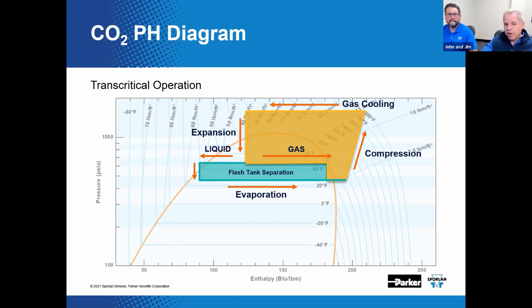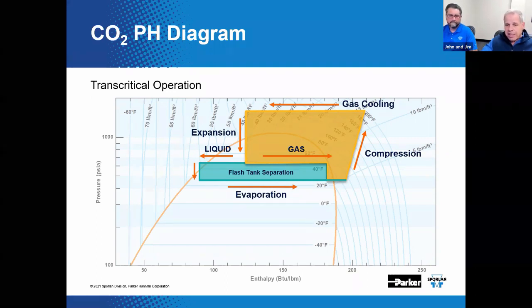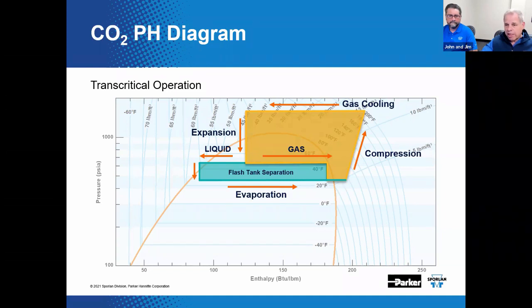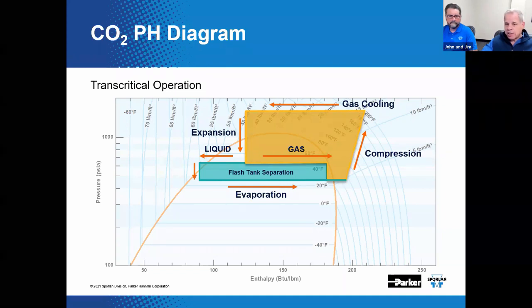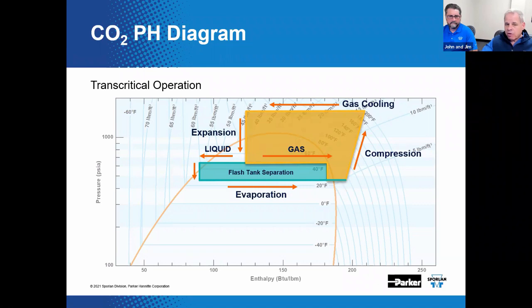The same evaporation and compression occur as in a DX operation because in a way it's a DX system. The big difference is instead of condensing superheated gas into a liquid, we are cooling a superheated supercritical gas into a cooler supercritical gas. And again, it's called gas cooling. And I guess that's what's going on right up here. Then we expand through the gas cooler valve into the flash tank.